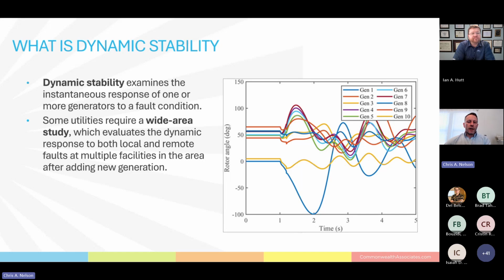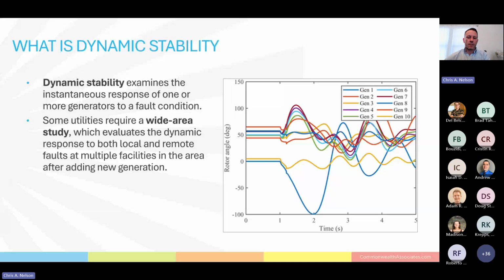To start with, I wanted to go over what dynamic stability is, what it looks like when things are good, what it looks like when they're bad, just a high level overview of it. So it examines the instantaneous response of usually a generator, but also loads can be modeled. If there's a fault or some sort of disturbance in the system, they should respond in a certain way. Usually there'll be a blip on the graph of what the generator is doing, and then it'll settle back down to its new normal. But if it's not behaving, it might go a little haywire.